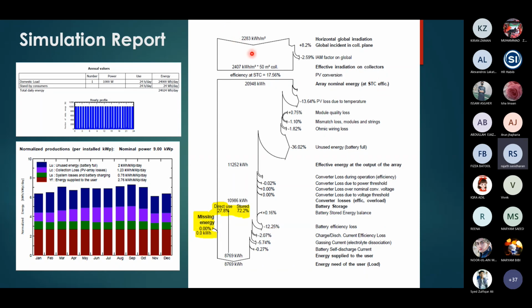Here you have 2,283 kilowatt hours per meter square available, because you have such a big catchment area. But there are several losses happening due to module mismatch and quality losses, the STC value versus actual conditions, and conversion losses when converting DC to AC. Some energy is stored, some is used directly, and this is the total energy you get out of the system.